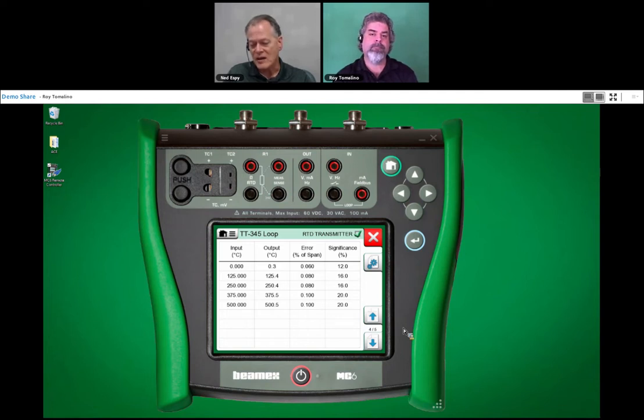So he actually had a quality improvement in his process. It really got rid of some huge headaches. And maybe if the dry block's off a 1/10 of a degree or whatever, he has all 6 zones measuring the same exact temperature. So there's a lot of cool things you can do especially with a temperature probe, because they can cause you all kind of headaches.